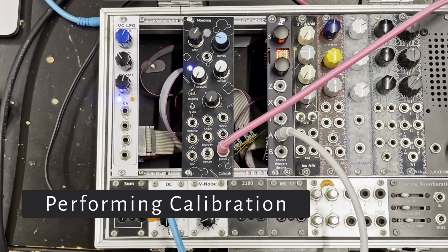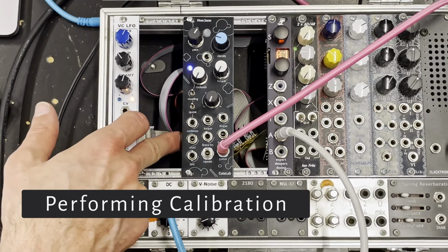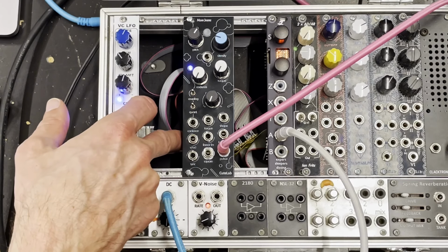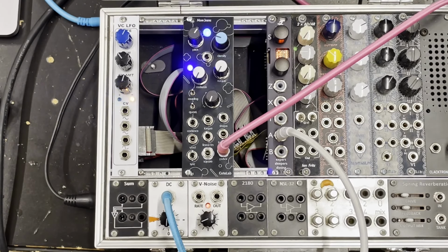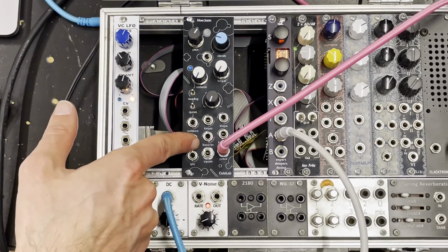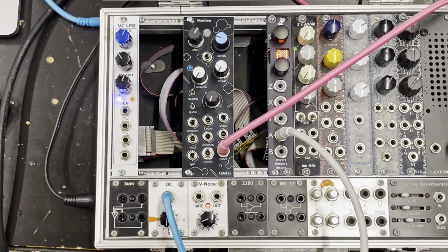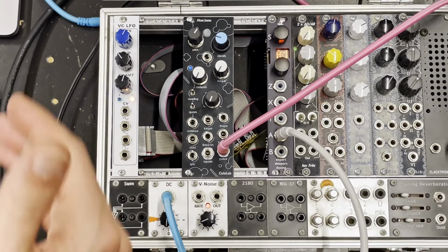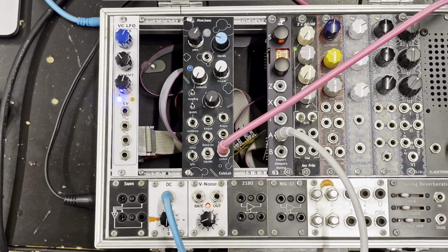Okay, let's actually do the calibration. So to do that, I'm going to press and hold calibrate, enter calibration mode. Right now we're in calibration mode 1. In calibration mode 1, all of the audio inputs are just expecting a 0. So they're all taking a reading right now and recording that as the 0 value. And that's useful later for when they get readings that are bigger than that. They'll know those are positive voltages. Smaller than that, they'll know those are negative voltages.